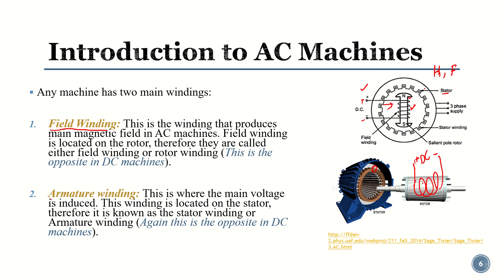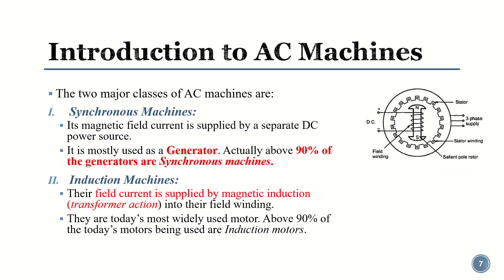The rotor winding is called the field winding, and the stator is also sometimes referred to as the armature. We also have coils on the stator. When the rotor is rotating and current is flowing, it induces a magnetic field. With a rotating magnetic field we have changing flux, which induces a voltage on the stator coil. The resulting current is called the armature current or stator current, and the winding is called the armature winding or stator winding.